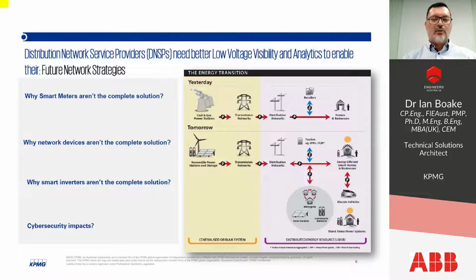So you might think, well, if each consumer had a smart meter, that would resolve the issue. Yes, that is true. And in Victoria, that certainly has been the case as it's been mandated, but that has not been mandated in the rest of Australia. So the consequence of that is that it costs between $10 and $15 per annum per meter for the DNSP to get access to that smart meter data outside of Victoria. And this can quickly add up to something in the order of $10-15 million if you had 100% network visibility.